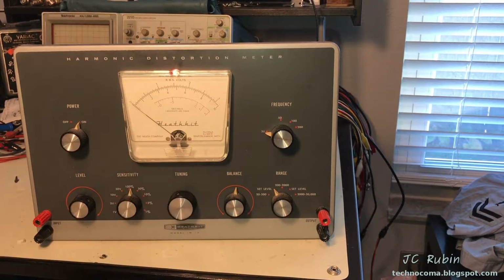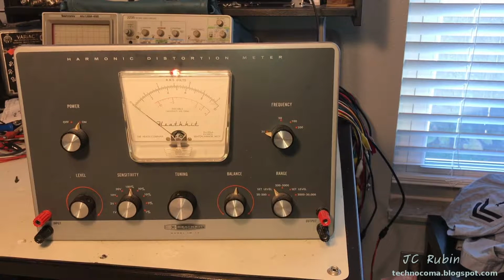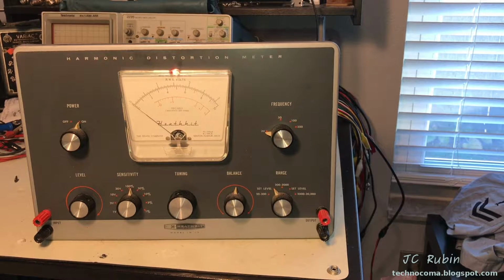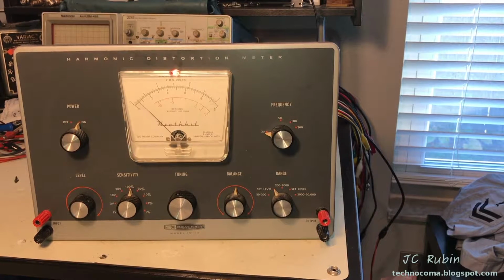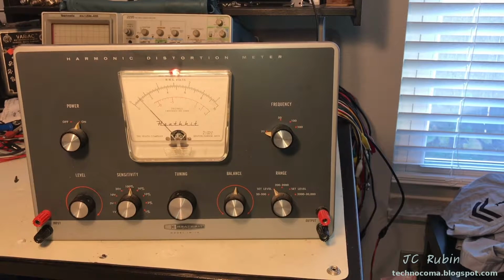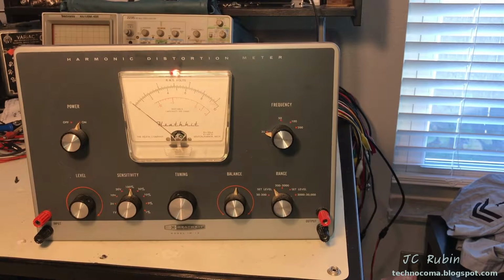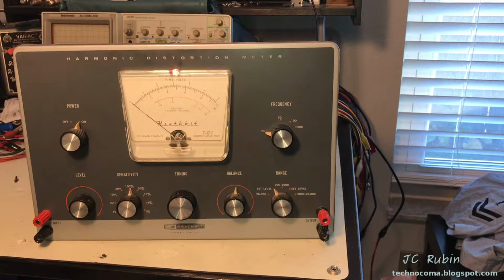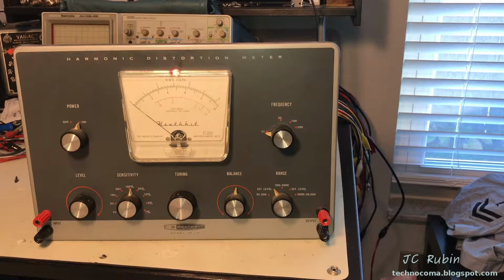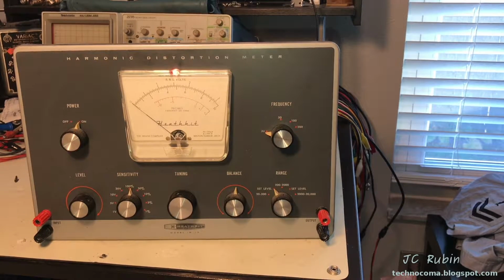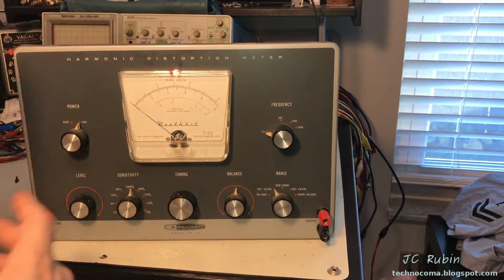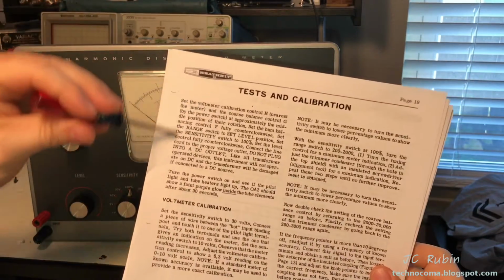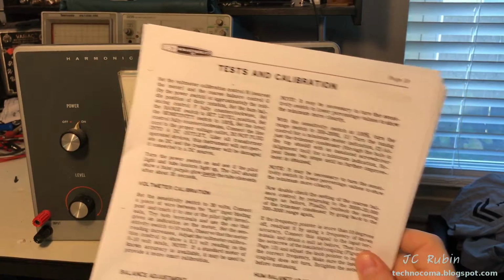I imagine the meter is probably going to bump initially as it warms up. After about 30 seconds, once it starts seeing some, there it goes. Meter moved. We'll see it settle back down. A visual inspection shows a faint glow coming from the OA2. So far we have gotten through the first paragraph right here, which is the setup for calibration.